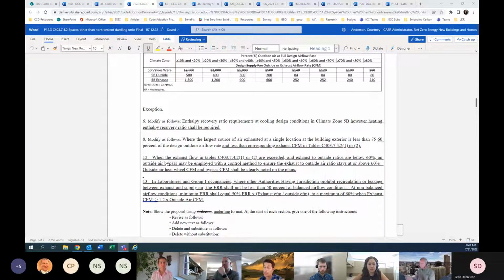And I've seen them on schedules, 1.5, 2 inches. And when you run through the math, it's just this parasitic load that, on a design day is okay, but it's the 45-degree day where you need to recover some heat that you're just chewing up fan energy and using more energy than you're saving.